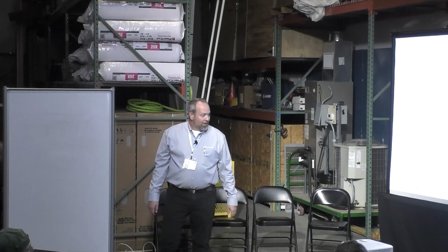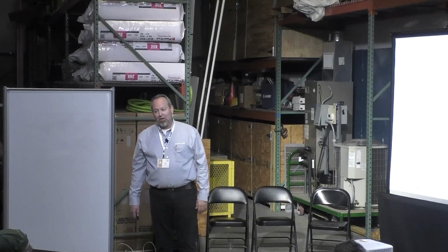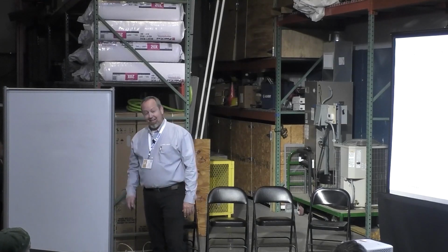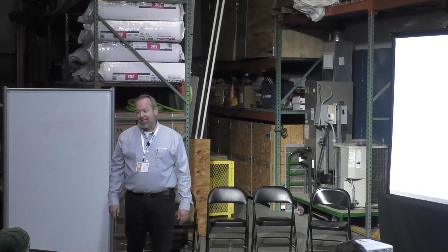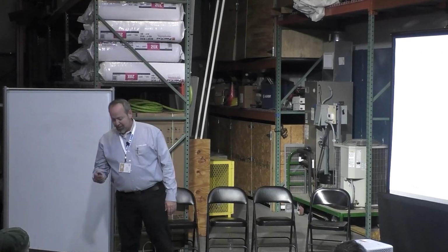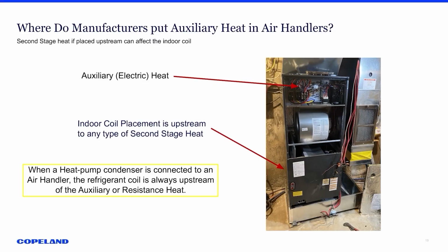So that is the recommendation on crankcase heaters and the importance they are needed to be in there if you're running a heat pump, especially if you're working on dual fuel. This is now getting more into the actual coil placement: how do you hook up a coil or install a coil for a heat pump if you have a gas furnace involved as well.